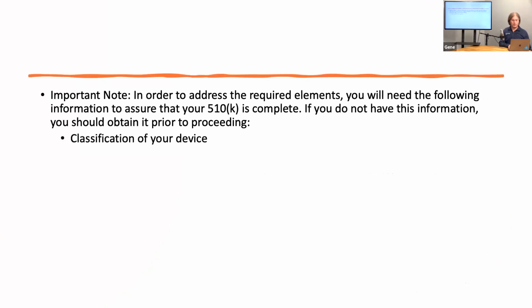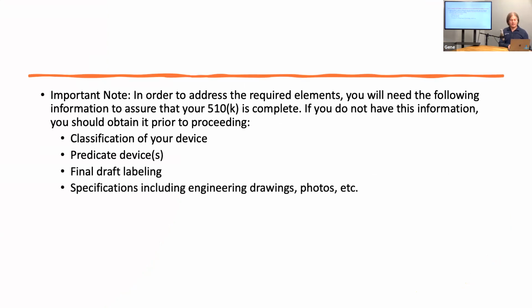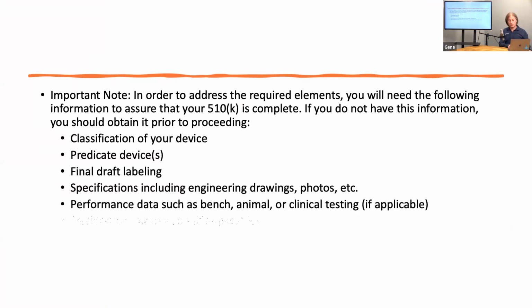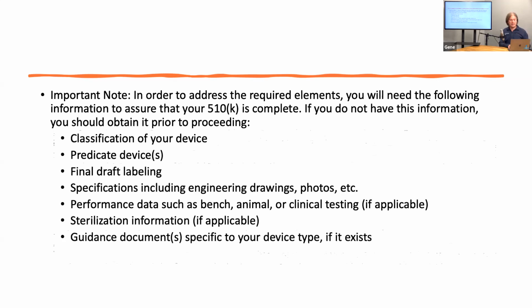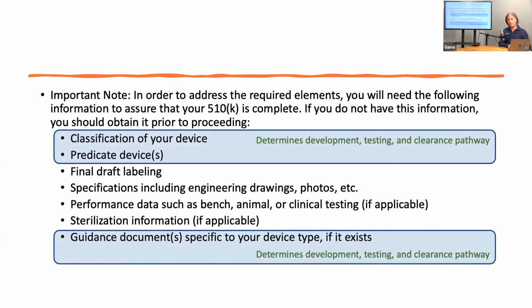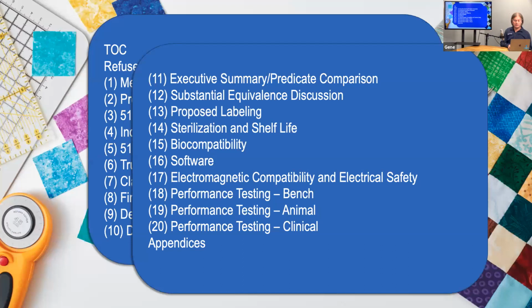And we talked over previous weeks about the kinds of things you need before you can set out to submit a 510K: classification and understanding of your predicate device, final draft labeling, specifications, performance data, sterilization information, guidance documents. But none of these are sufficient in and of themselves to be ready to submit. You have to take these and let them feed into your development and into your testing and into your clearance. You have to generate a mature design history file that can feed into that submission when it actually comes time to put it together. And last week we covered the 20 sections plus table of contents and checklist and the appendices that actually go into a 510K submission.